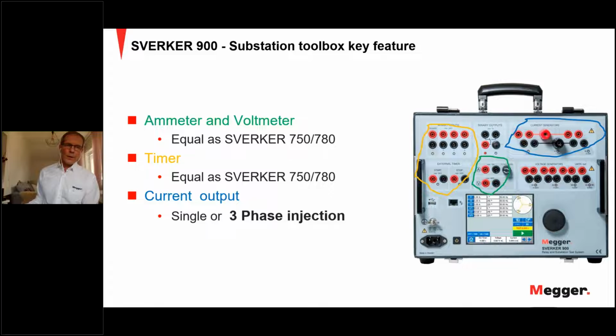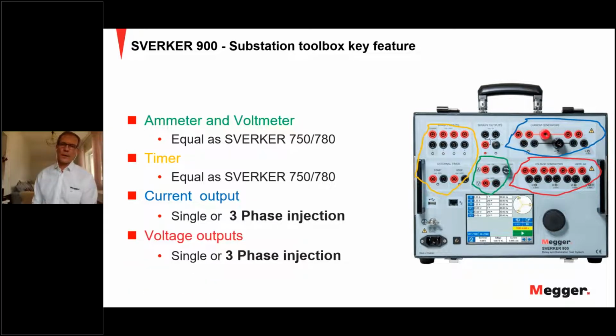Also, we have the output for voltage, and the voltage output is the same there. It is possible to inject three-phase from the voltage output, and actually we have 4 voltage outputs on SVERKER 900, and they can be used individually. And then you can set the SVERKER 900 in single phase mode and connect them in serial or in parallel with the jumpers, and then you can also get very high amplitudes, or you get a lot of power from this when they are running together.